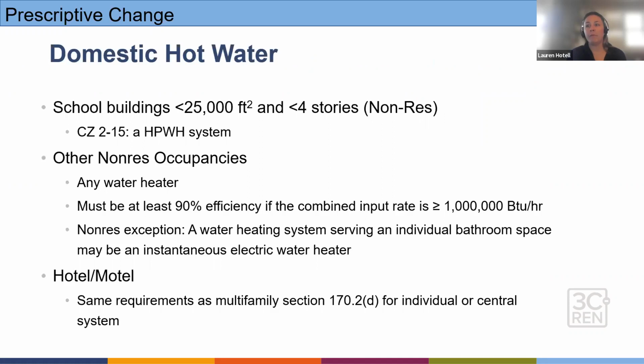Similar to what Amy was touching on non-res, we are trying to use a heat pump water heater system wherever possible. So school buildings that are less than 25,000 square feet and less than 4 stories would be required to use a heat pump water heater system as long as you're within climate zones 2 through 15. Any other non-residential occupancies, you can use any water heater. It has to be at least 90% efficient if the combined input rate is at least 1 million BTU per hour.